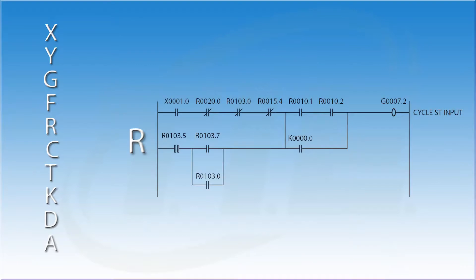There are other addresses used in the ladder logic. The one you will see most often is the R address. It is used as a register in the ladder. Basically, they serve as temporary coils and contacts used in the ladder for decision-making purposes. They do not have a real world input or output capability. In other words, don't look to hook up a connection to them.